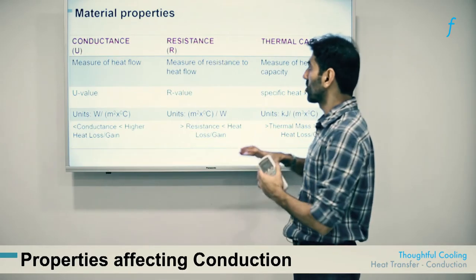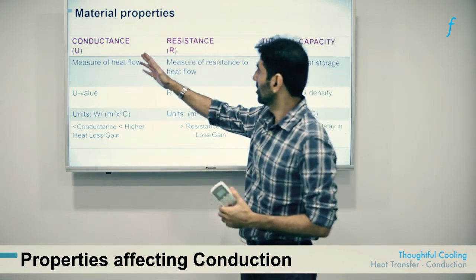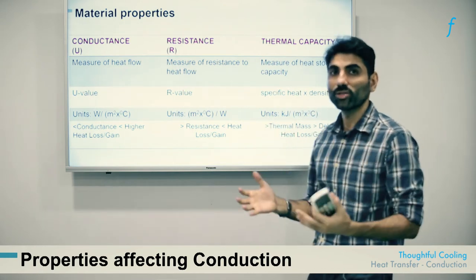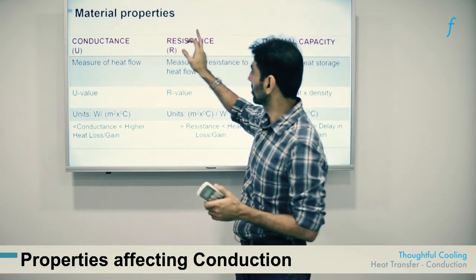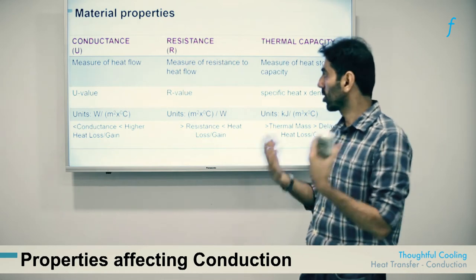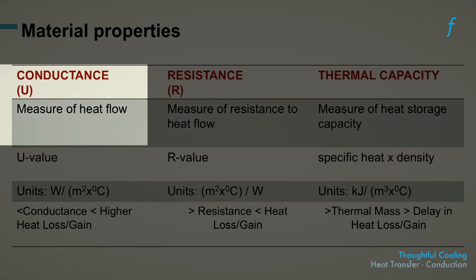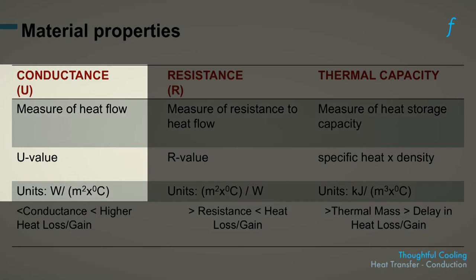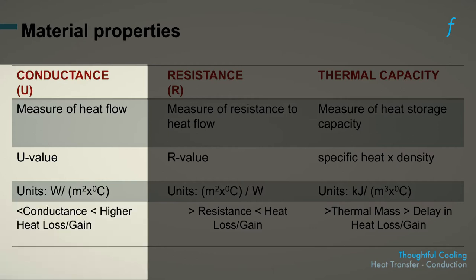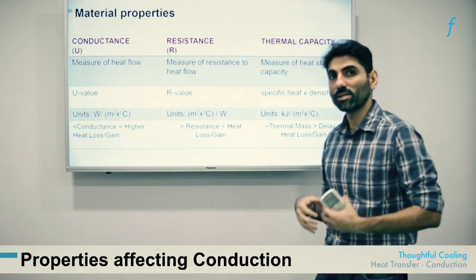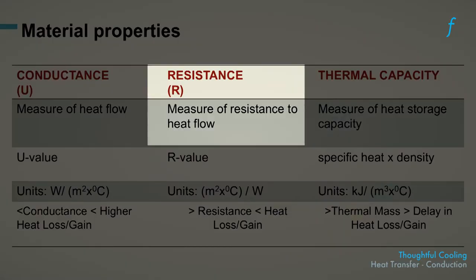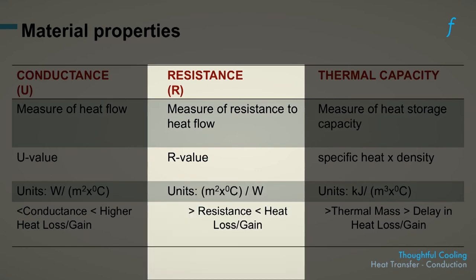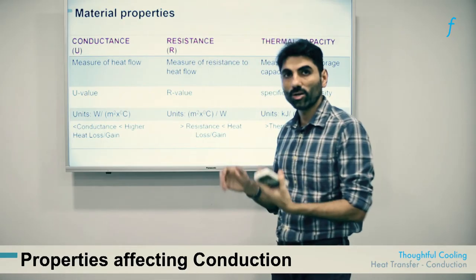To encapsulate and summarize all the thermal properties discussed: conductance, resistance, and thermal capacity all have relations with heat transfer but are distinctively different phenomena. Conductance is the measure of heat flow, signified by the U value with units of watts per meter square degree centigrade — the lower the conductance, the lower the heat gain, which is beneficial for a thoughtfully cooled building. Resistance is the exact inverse of conductance — the greater the resistance, the lesser the heat gain — so the goal is building materials with high resistance to prevent heating up.